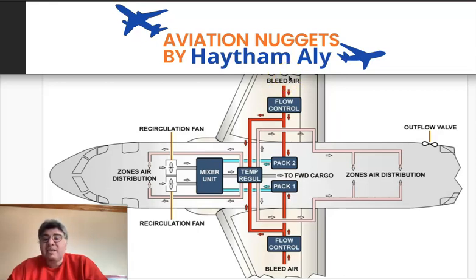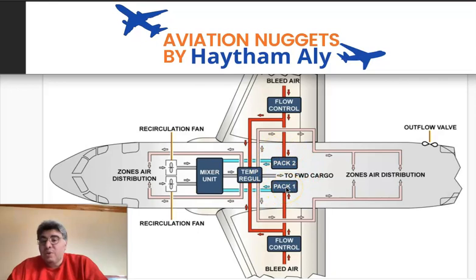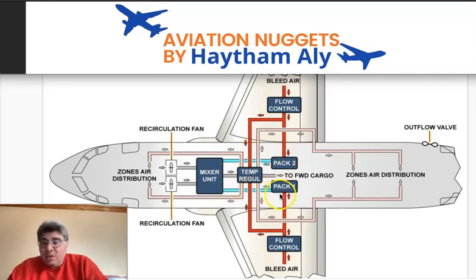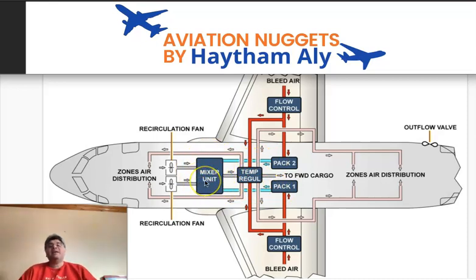The bleed air passes through pressure and temperature regulation components, then through a flow control valve — which is the on/off valve for each pack. The packs then perform basic temperature regulation, and their cold air output is supplied into what is called a mixer unit.